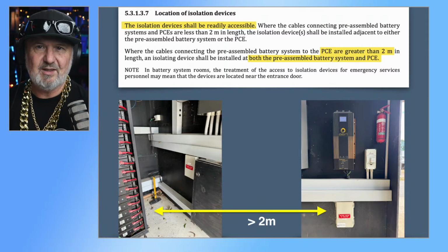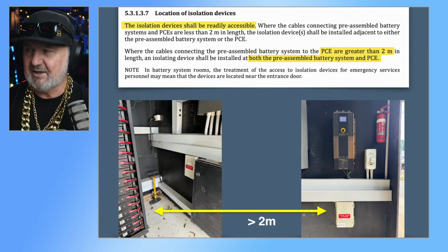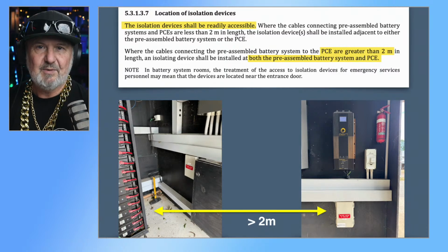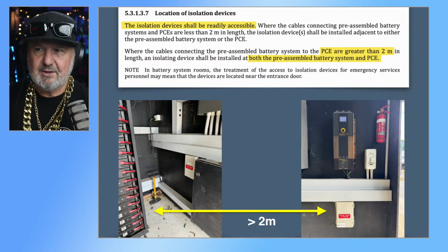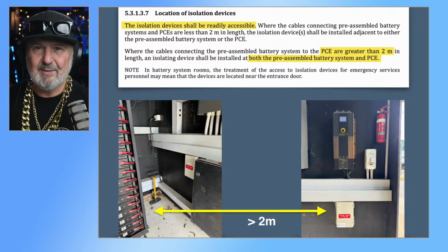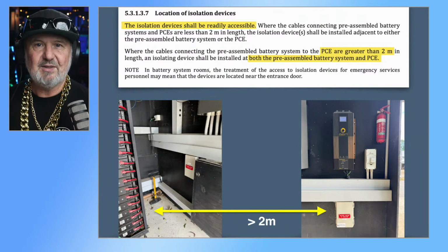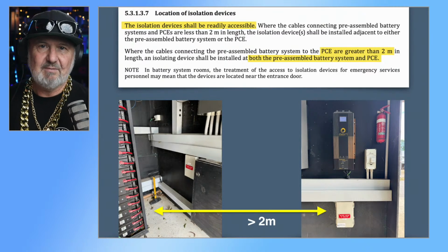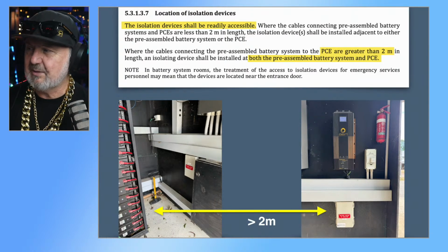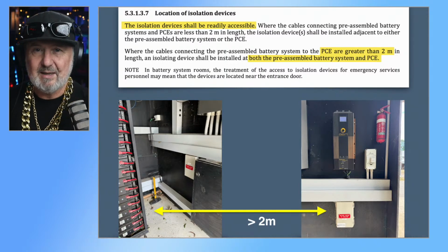So the idea of an accessible switch or isolator in this case is so that the non-authorized workers can switch stuff off. They don't need to have a special tool to get to it. So a main switch, for instance, is readily accessible. And I like to kind of just remind myself the difference between accessible and available. So accessible is like you can roll up to it in a wheelchair. That's accessible and operate that switch. You don't have to have a special tool. But readily available is for maintenance and repair. So we need an accessible isolation device. So it can't be embedded inside the unit that you need to unscrew to get to.